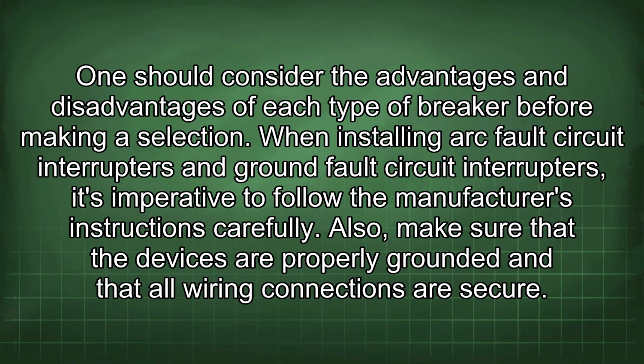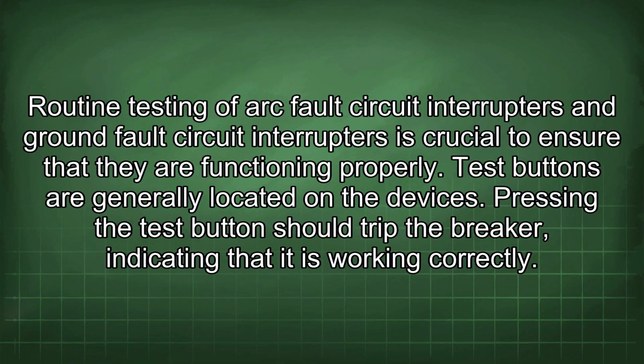When installing arc fault circuit interrupters and ground fault circuit interrupters, it's imperative to follow the manufacturer's instructions carefully. Also, make sure that the devices are properly grounded and that all wiring connections are secure. Routine testing of arc fault circuit interrupters and ground fault circuit interrupters is crucial to ensure that they are functioning properly. Test buttons are generally located on the devices.